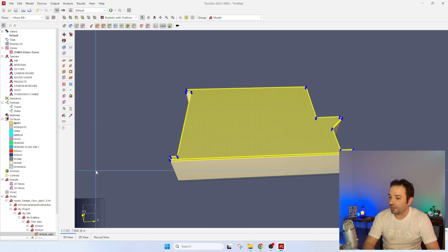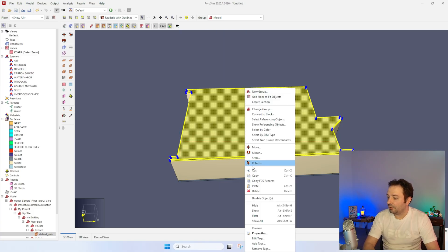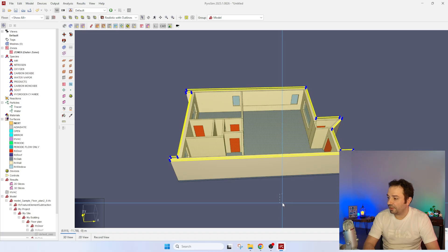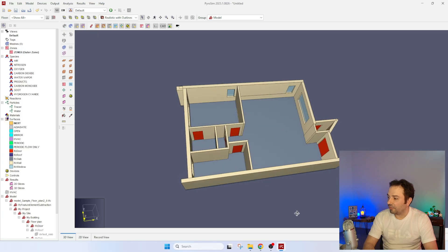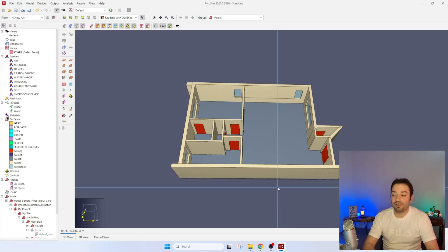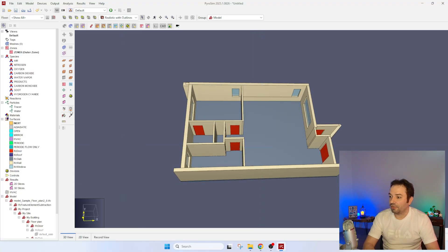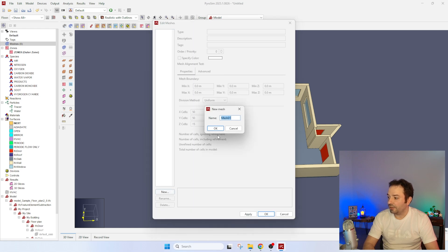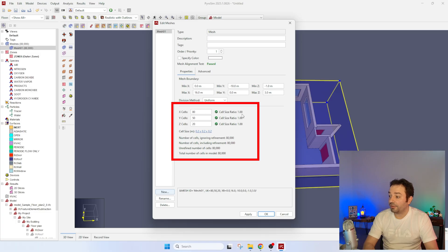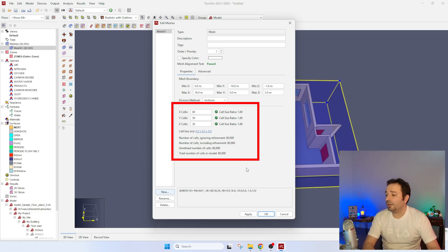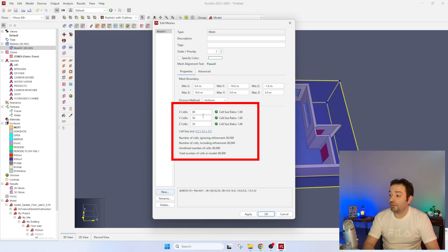Let's go and have a look inside. I'm going to select the roof, right-click, and hide it from the geometry. You can see the building is represented in a really cool way — I'm really pleased with it. Next, I'll add the mesh by double-clicking on meshes and generating a new mesh. It's already all done automatically by PyroSim using symmetric cells of 20 centimeters by 20 by 20. If you want higher resolution, you can change this setup.